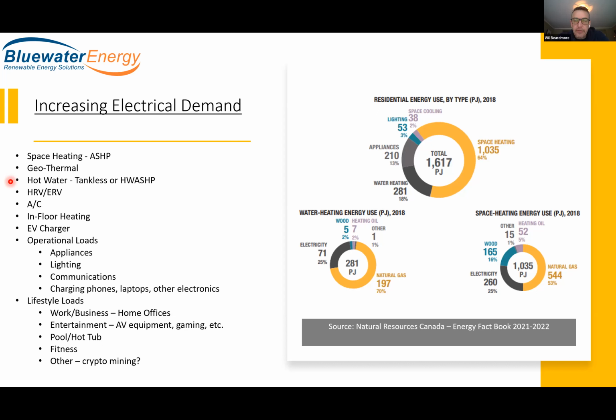And that's not just moving from a 200 amp to a 400 amp panel. That's moving from a 200 to a 400 amp service, which means the meter base is now 400 amp rated, and the conductors coming in from the road, from the transformer, are 400 amp rated. All of that infrastructure needs to be upgraded to facilitate that, and that's where the extra cost comes in, which is what we're trying to avoid.